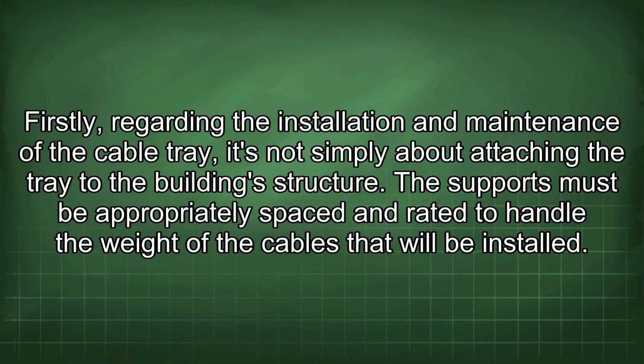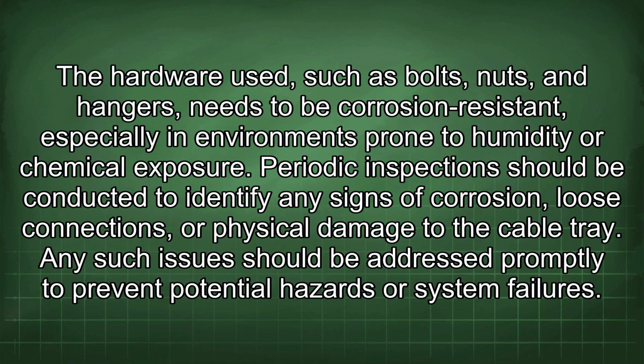Firstly, regarding the installation and maintenance of the cable tray, it's not simply about attaching the tray to the building's structure. The supports must be appropriately spaced and rated to handle the weight of the cables that will be installed. The hardware used, such as bolts, nuts, and hangers, needs to be corrosion resistant, especially in environments prone to humidity or chemical exposure. Periodic inspections should be conducted to identify any signs of corrosion, loose connections, or physical damage to the cable tray. Any such issues should be addressed promptly to prevent potential hazards or system failures.